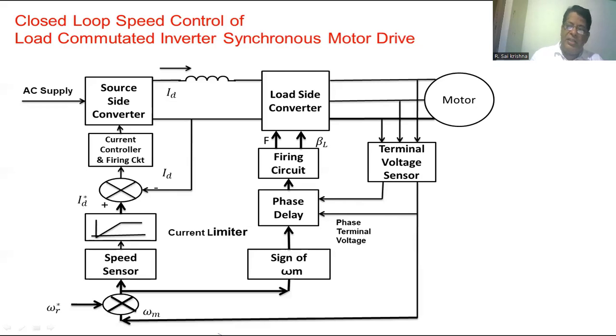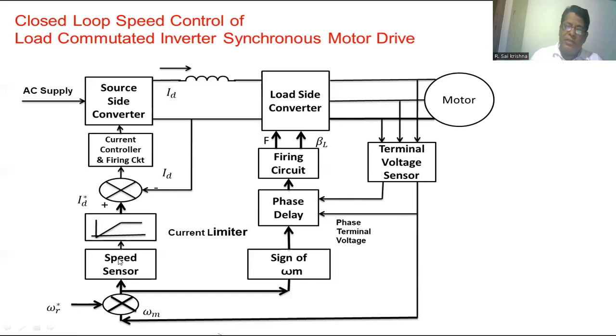If the reference speed is decreased, the actual speed of the synchronous motor is higher, so the speed error becomes negative. When the speed error is negative, the commutation advance angle is set for regenerative braking operation of the load side converter, and the motor speed decreases. Once the speed decreases, the error between the reference speed and actual speed reduces. This is again processed by the speed controller, which sets the current limiter to a value where the load torque equals the developed torque in the synchronous motor. In this manner, we change the speed of the synchronous motor from one value to another at a constant commutation advance angle and maximum torque development, so that the transient time of the motor operation is minimized.